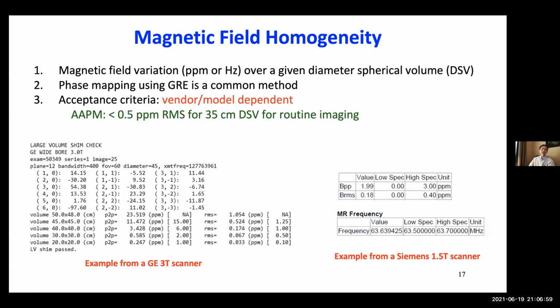So for example, even within a vendor, different models can have different criteria, whether it's a narrow bore or wide bore scanner, their homogeneity criteria are different. But anyway, AAPM also provides a general recommendation of about 0.5 ppm root mean square for a 35 centimeter diameter spherical volume. Okay, here I'm showing you two results from vendors. When the vendor comes in to do routine preventive maintenance, they usually check the shim, and that provides the homogeneity result.